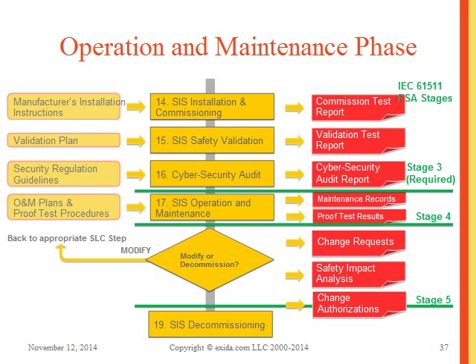The operation and maintenance phase begins with validation of the design. This validation must answer: Does the system solve the problems identified during hazard analysis? Have all necessary design steps been carried out successfully? Has the design met the targeted SIL for each safety instrumented function? Have maintenance procedures been created and verified? Is there a management of change procedure in place? Are operations and maintenance personnel qualified and trained? All of these must be acceptable before proceeding into start-up and operation.